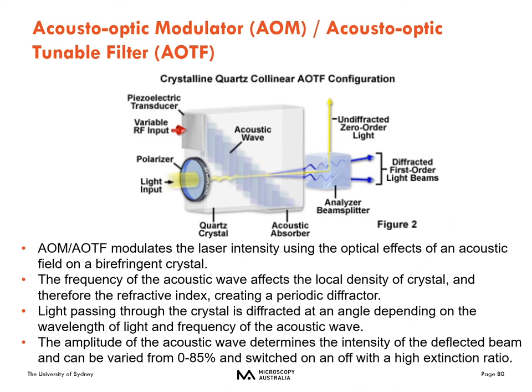We typically prefer to use an Acousto-Optic Modulator or Acousto-Optic Tunable Filter. An AOM adjusts laser intensity using the optical effects of an acoustic field on a birefringent crystal. By inputting radiofrequency waves onto the birefringent crystal, we affect the local density and therefore the refractive index. Light passing through the crystal is diffracted at an angle depending on the wavelength of light and the frequency of the acoustic wave. The amplitude of this acoustic wave determines the intensity of the deflected beam and can be varied between 0 and 85 percent. You can basically switch your laser on and off very quickly — this works very well for beam blanking. Maybe you only need 10 percent of that full laser power, so you can turn it on at 10 percent.